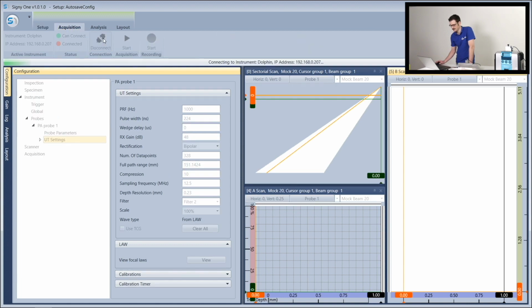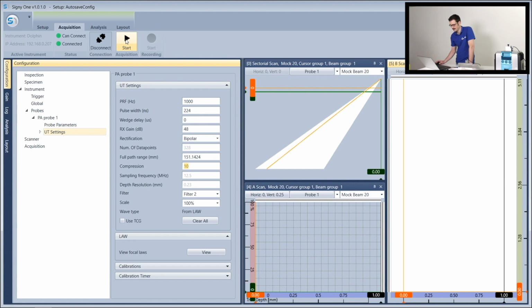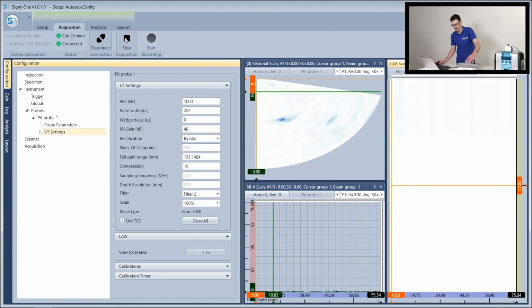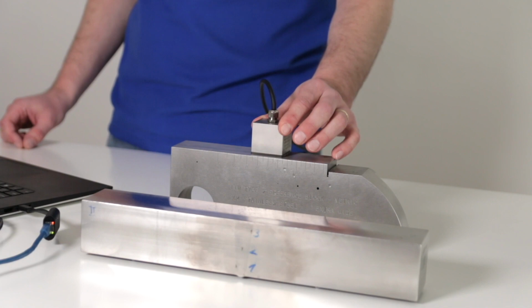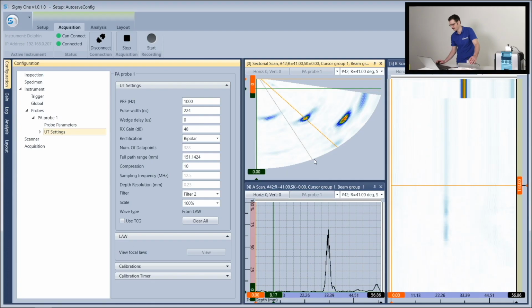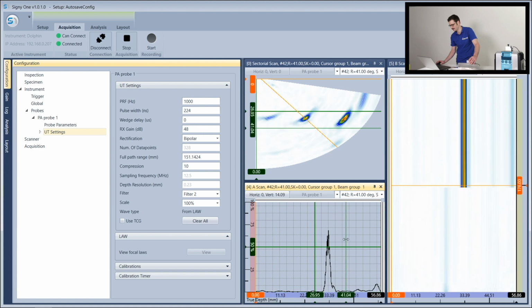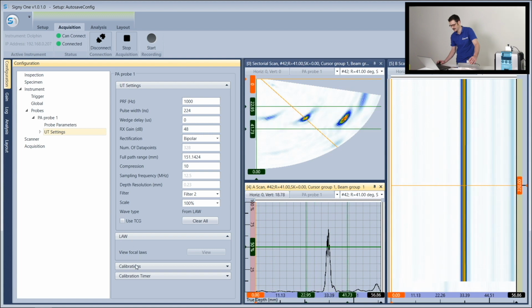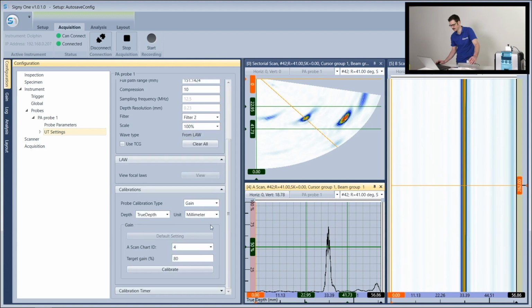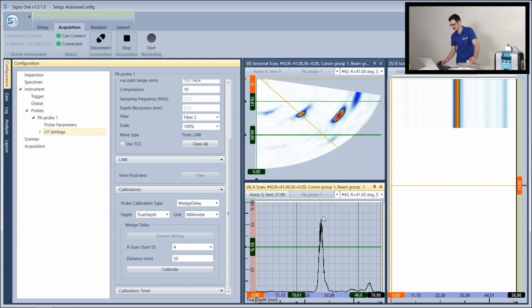First I need to connect to the instrument, and then click start. The probe is on the reference block with 3 side drill holes at 30 mm depth. I will be calibrating the wedge delay on the middle side drill hole. I select the area of the peak, I go to calibration, I select wedge delay, the probe is at 30 mm depth. The peak is now at 30 mm depth.